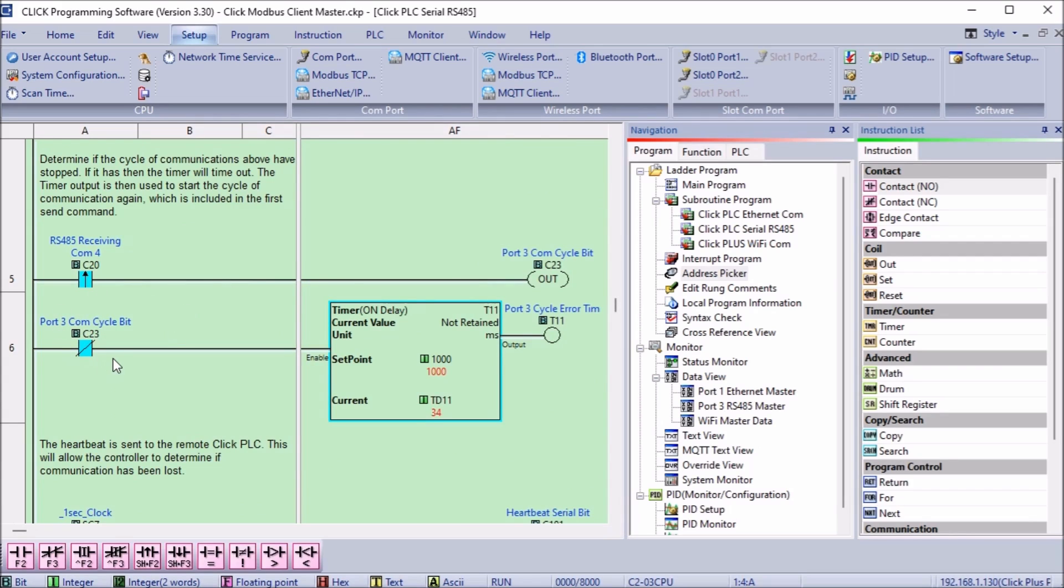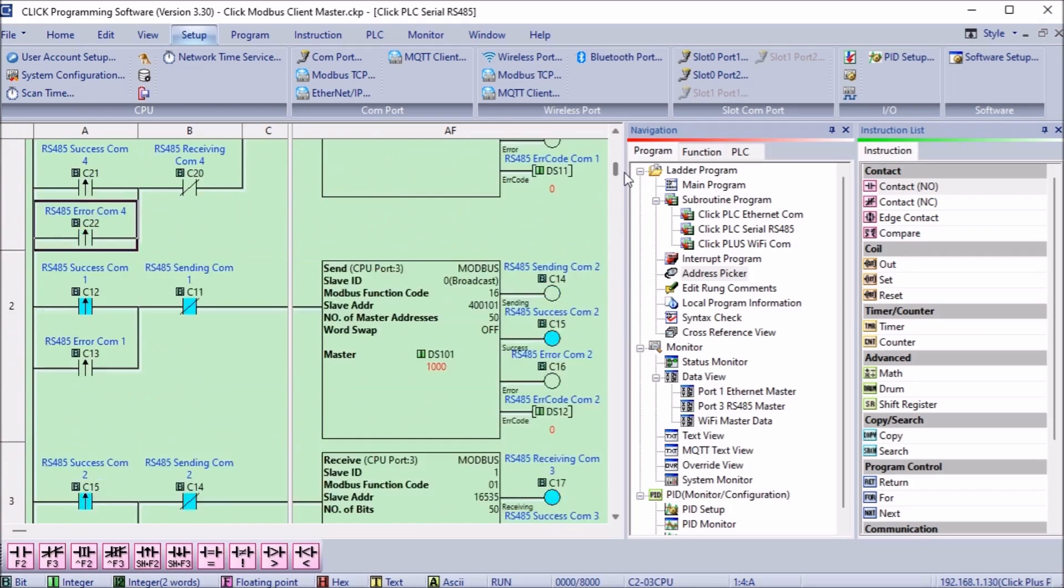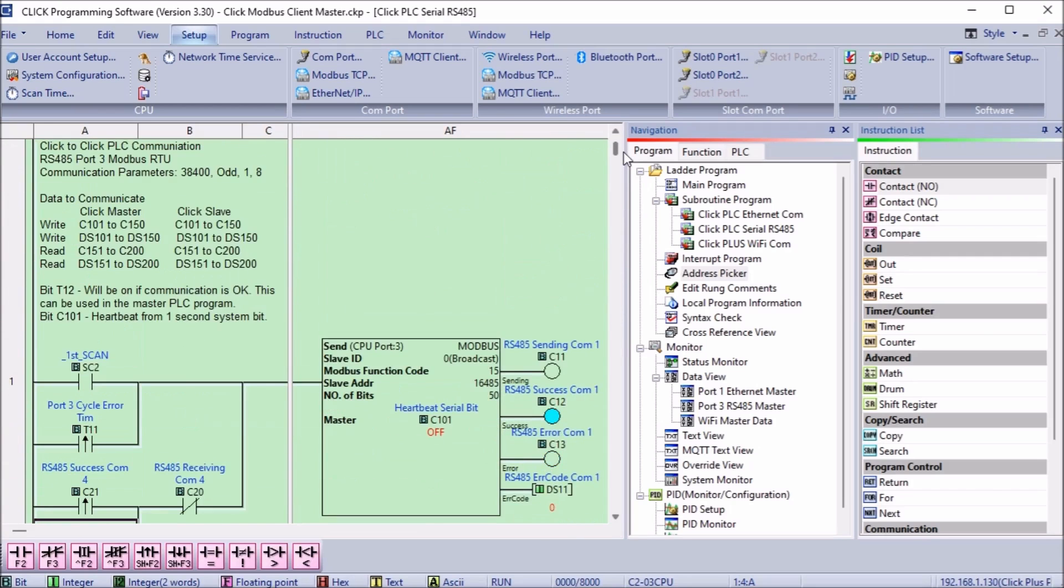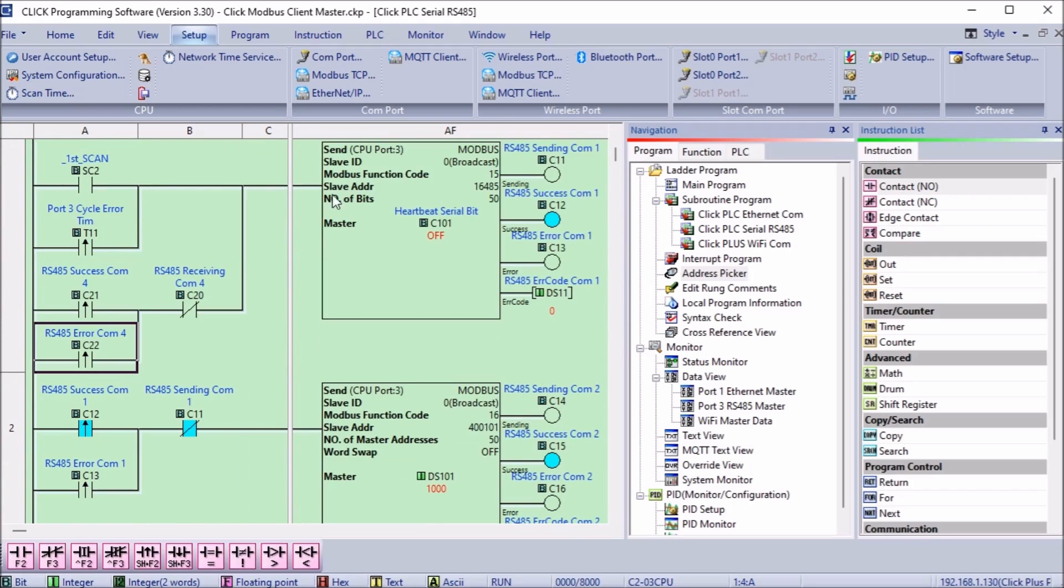The normally closed of this bit will then start a timer set for 1000 milliseconds or one second. The leading edge of this timer bit will then start the first instruction again in parallel to the first scan instruction. We will now ensure that the information will continue to be updated.